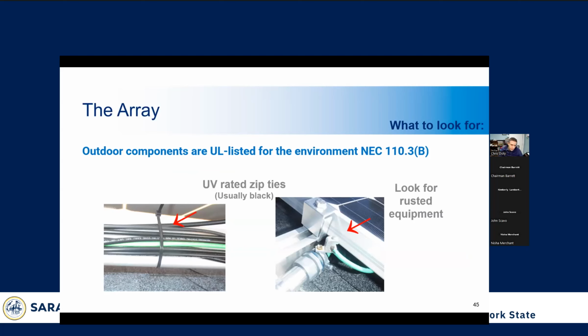So here we're continuing on with the array. Again, it's critical to use outdoor rated equipment. Here we have a situation where wires were bound up using a UV rated zip tie. The white ones are typically not UV rated, and they can degrade in the sun over time. Eventually they'll get brittle and break, and then you just have a bunch of wires hanging down on the shingles. Shingles are pretty abrasive, so as they're moving around in the wind and things, they'll wear away, and then you'll have exposed copper conductors, which of course we all want to avoid, right?